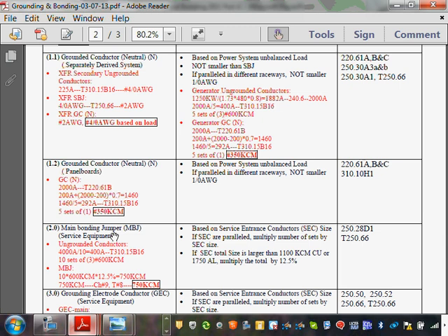Being an engineer, I put a big question mark here, guys, because when you put 10, this is okay if your feeder is coming overhead. If your feeders are going underground, you have trapped heat. If you're going overhead with the feeders, 10 runs overhead, EMT conduit or rigid or PVC, overhead no problem, exposed to the air, cool, good. You put them underground in ducts, then you have to encase them in concrete because of stability and all this good stuff. Then we have a software called AmpCalc that will come up with a larger size than this because of the heat interaction between all these cables and the heat trap in Mother Earth.